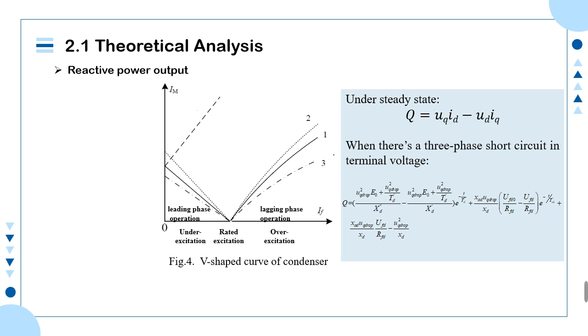There are two types of operating modes for LSC. Depending on the excitation, they are divided into two regions. In leading phase operation, LSC absorbs inductive reactive power from the system. In other words, reactive power output is capacitive. While in lagging phase operation, LSC will output inductive reactive power to compensate the system. The formulas for calculation are shown on the slide.